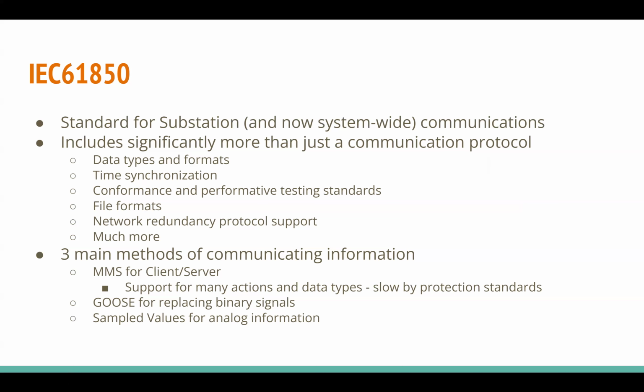The ones that are different for a digital substation than a conventional substation are these two, GOOSE and sampled values. Essentially, GOOSE is for replacing binary signals, the things like your breaker control or your breaker status. Sampled values is for replacing your analog hardwired signals. Instead of needing a hardwired cable for your voltage or your current, now you would send it with a sampled value stream over an Ethernet-based network. The same goes for GOOSE messages, which are sent over an Ethernet-based network.